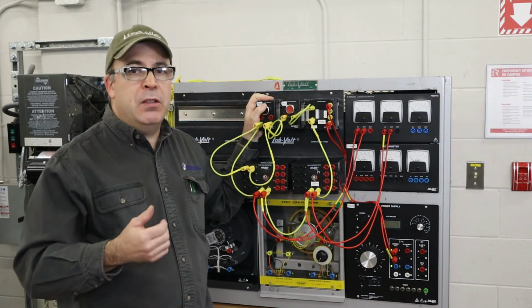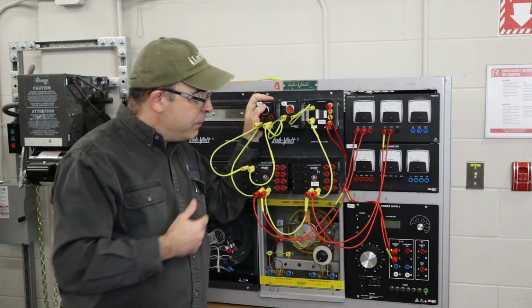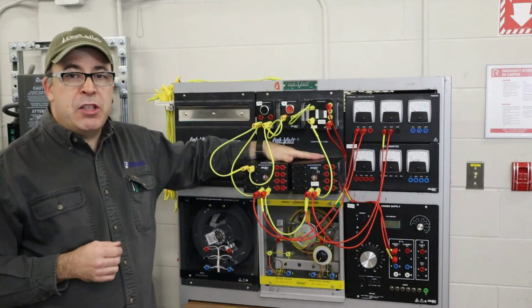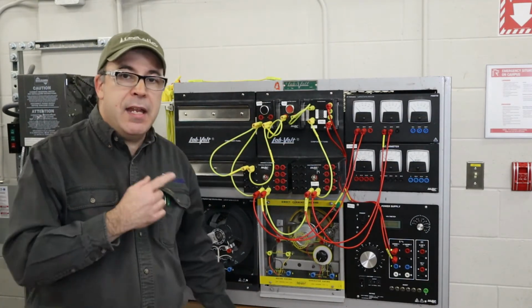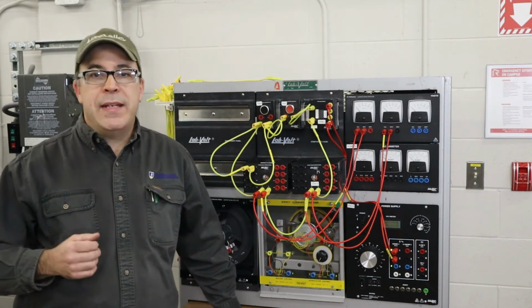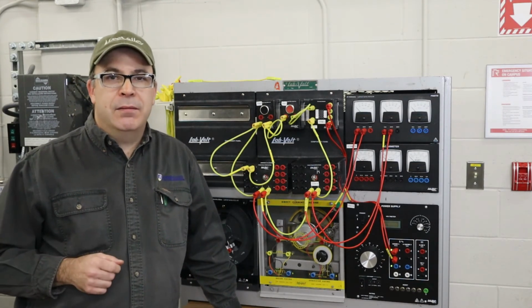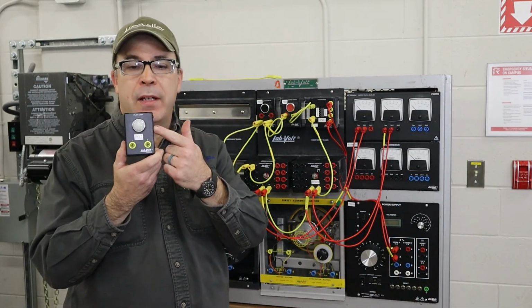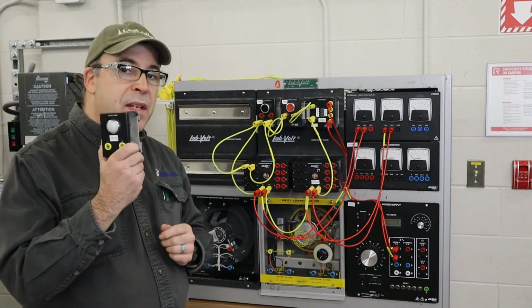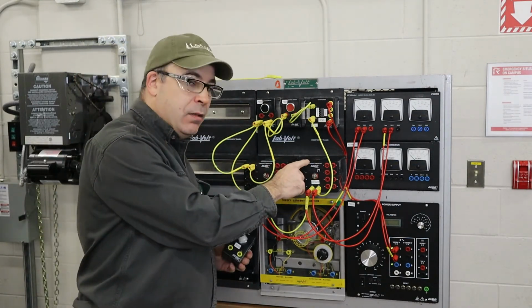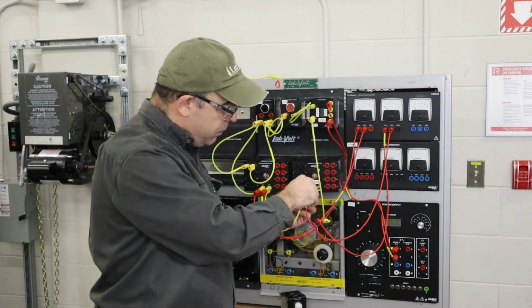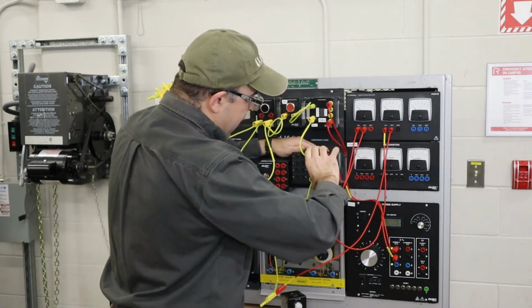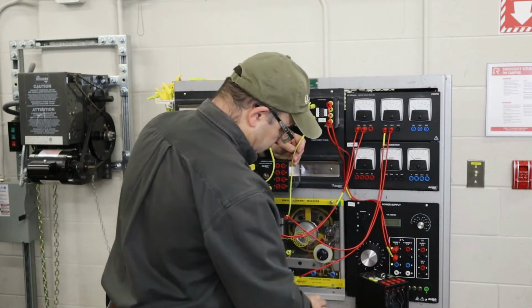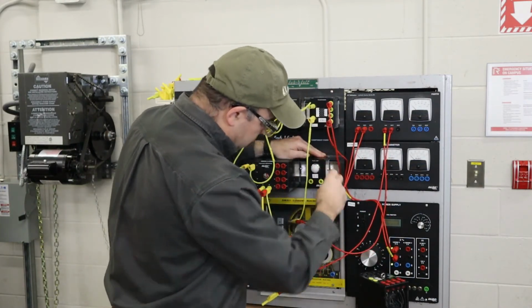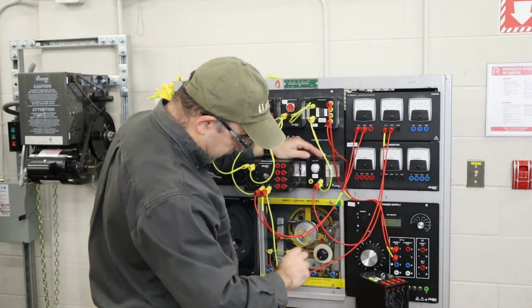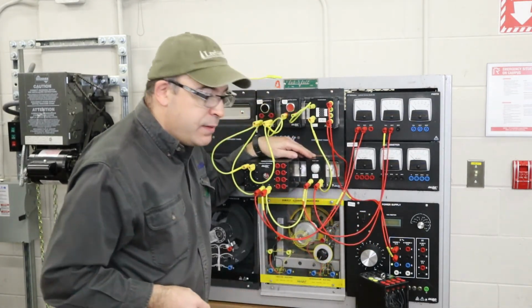Now, some people may be a little bit skeptical. What if, instead of using 2 contactors, what if I change this up and I used a contactor and an indicator light? Would we get different results? Let's try it and see. So I have an incandescent indicator light here, and what we're going to do is we're going to substitute the indicator light for the second contactor. Just a matter of disconnecting it, removing it from the panel, and mounting our indicator light and wiring it in series.